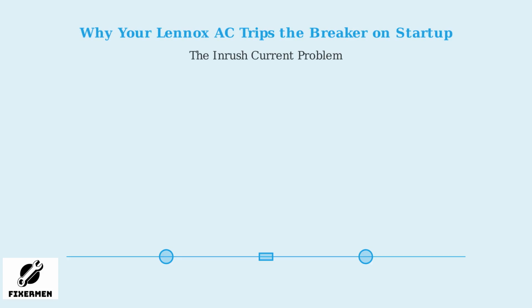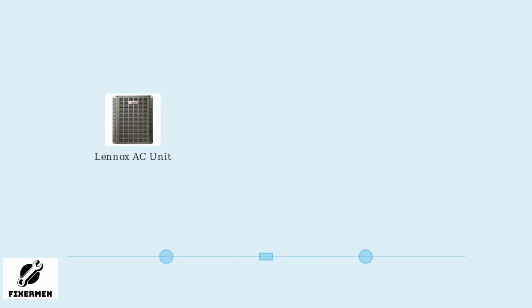Lennox air conditioning units often trip circuit breakers during startup due to a phenomenon called inrush current. This is a surge of electricity that occurs when the compressor motor begins operating. Here's what a typical Lennox AC unit looks like. These units are common in homes and businesses, but they can cause electrical issues during startup.